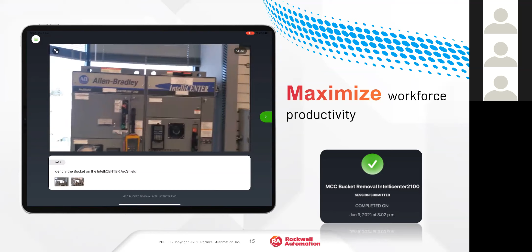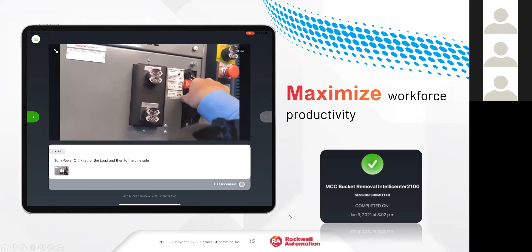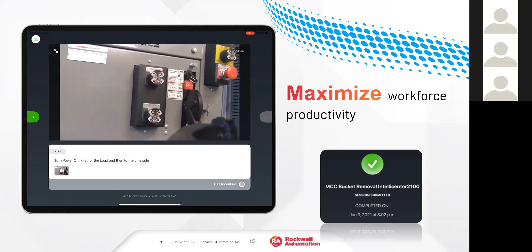The first thing we want to do is turn the power off to the bucket with the disconnect, making sure that everything is ready to do so. Motor disconnect is off. You'll notice that the load side power indicator is not showing any power, but the line side still is because we're still connected to the horizontal bus in the back of the MCC.